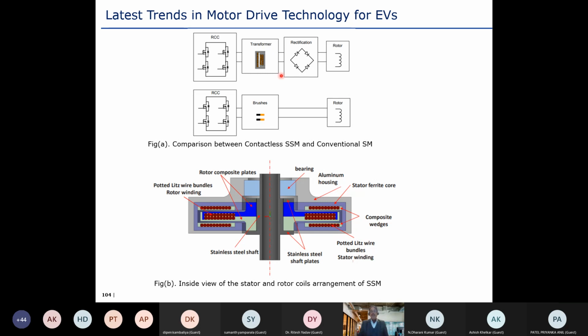But here, what we are doing is using a rotary transformer, and we don't need any auxiliary alternator on the same shaft, because that increases the weight, cost, and space. Here this rotary transformer feeds into the rectifier, and then the rectifier controls the current flowing in the rotor winding. This is the diagram you see.